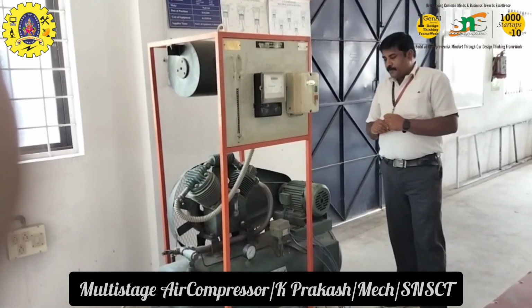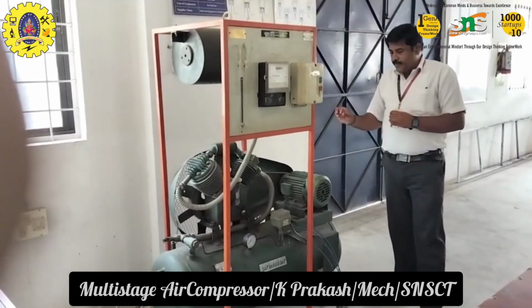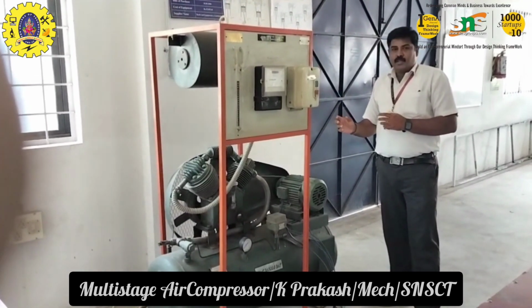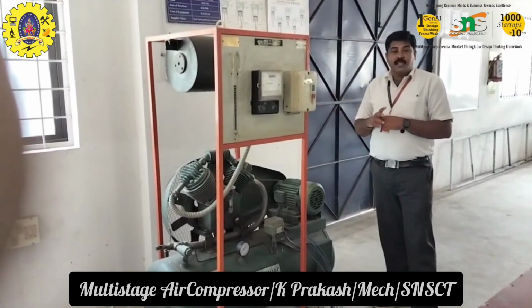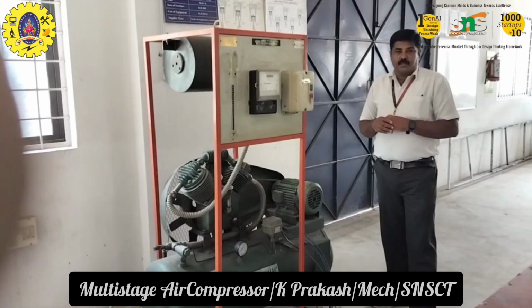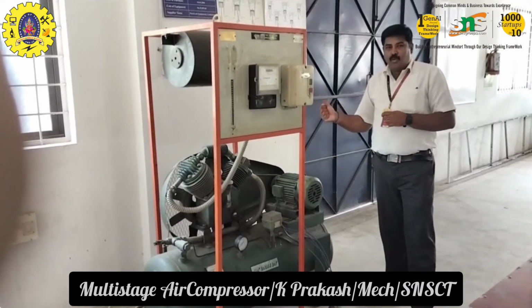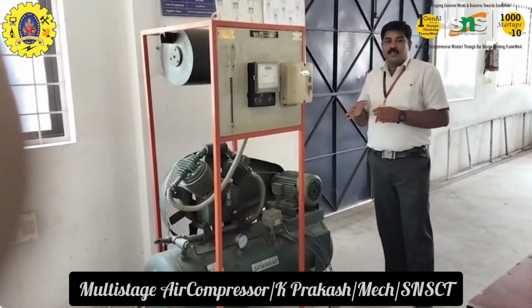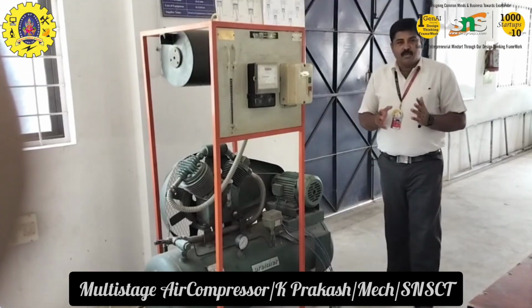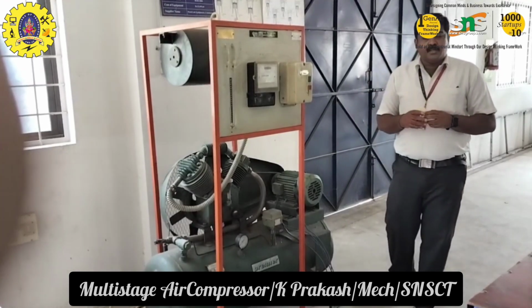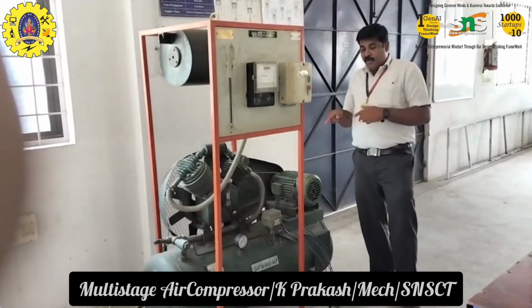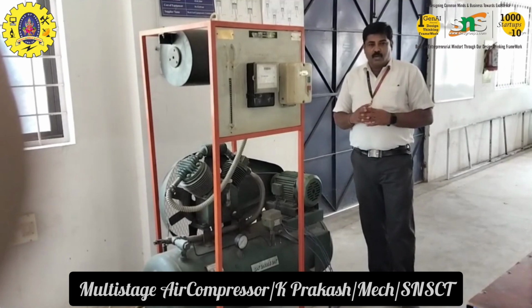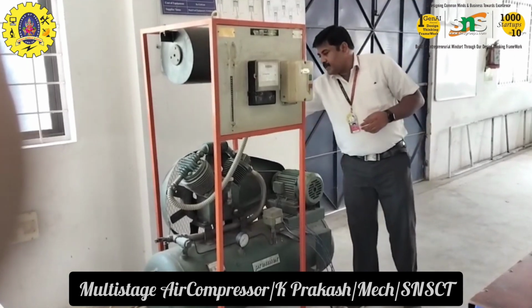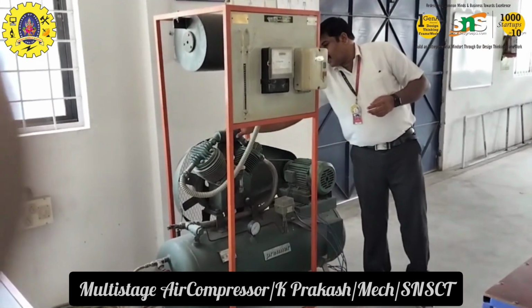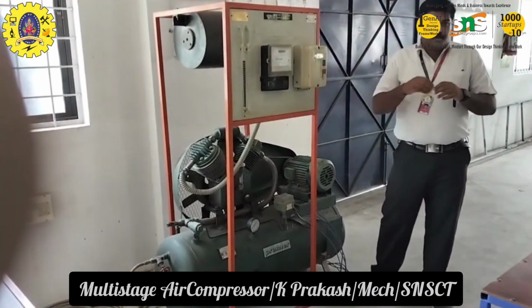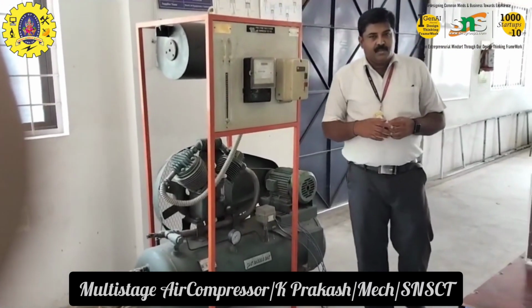In multi-stage compression, the purpose of the intercooler is to remove the excess heat during the compression. When the excess heat is removed, the work done is reduced, because the excess heat formed directly adds to the work done. This intercooler has projections called fins.